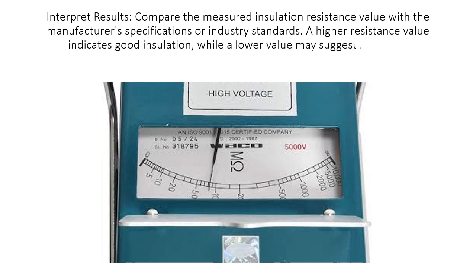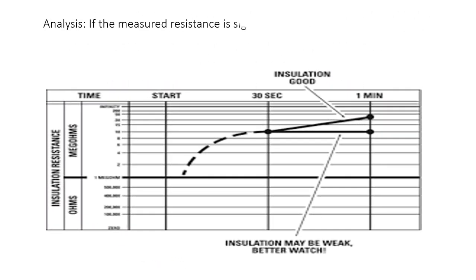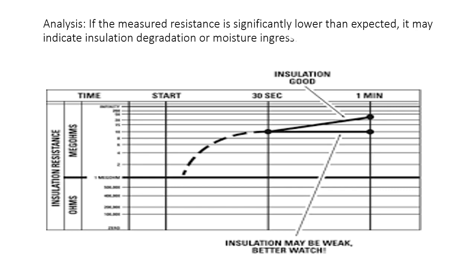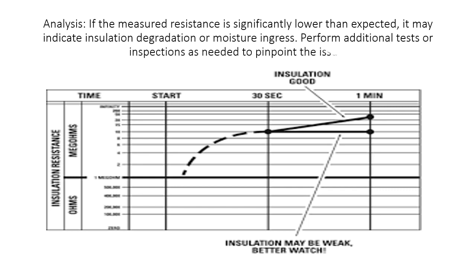Interpret Results: Compare the measured insulation resistance value with the manufacturer's specifications or industry standards. A higher resistance value indicates good insulation, while a lower value may suggest insulation deterioration or a fault. If the measured resistance is significantly lower than expected, it may indicate insulation degradation or moisture ingress. Perform additional tests or inspections as needed to pinpoint the issue.